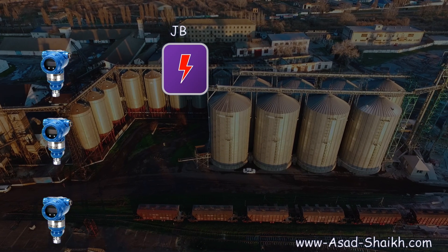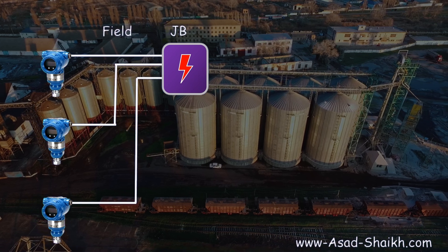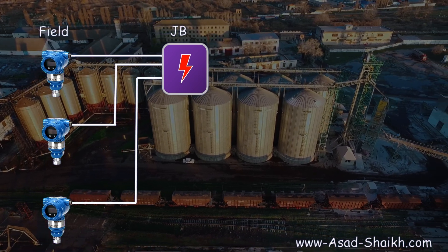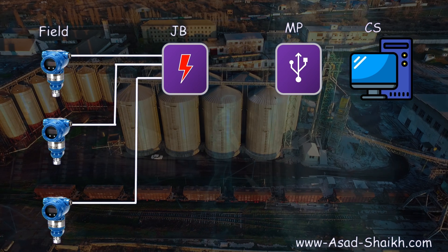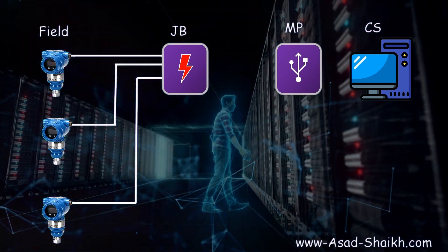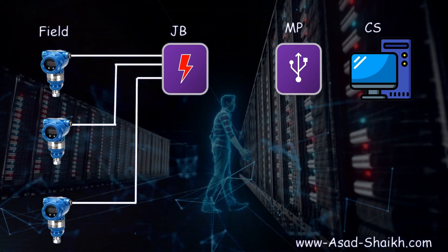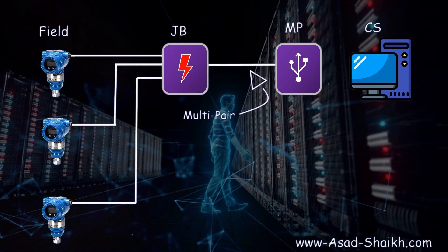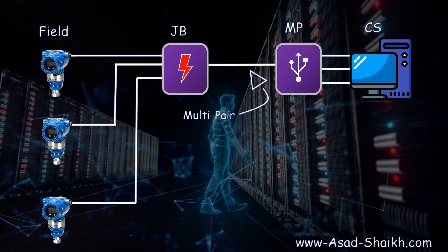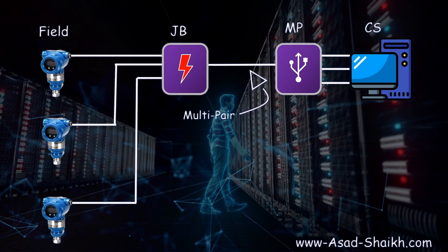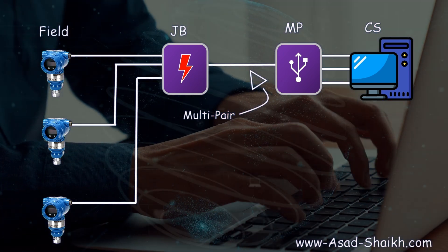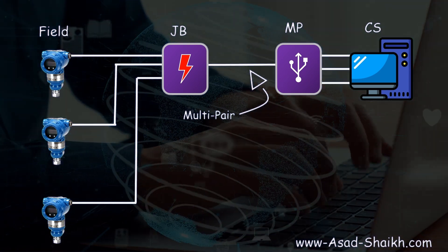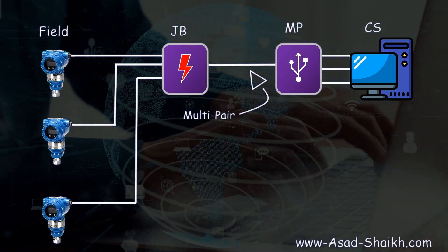To understand where the junction box fits in the overall big picture: various transmitters in the field are connected to your junction box. From the junction box in the field, you go to your marshalling panel, and from the marshalling panel to your control system. The cable from the junction box to the marshalling panel is generally a multi-pair or multi-core cable, and the control system will have AI, AO, DI, and DO cards. In this video we will focus on the JB part.